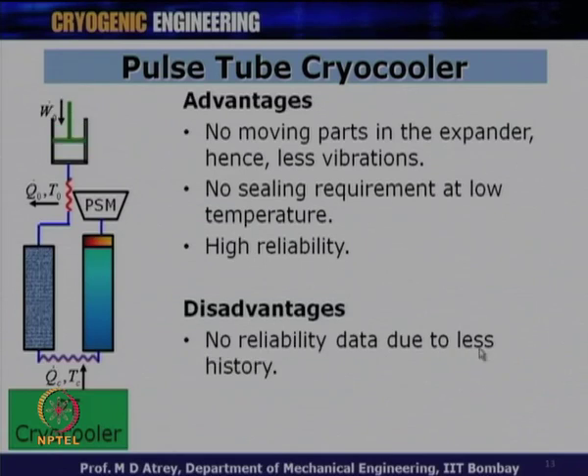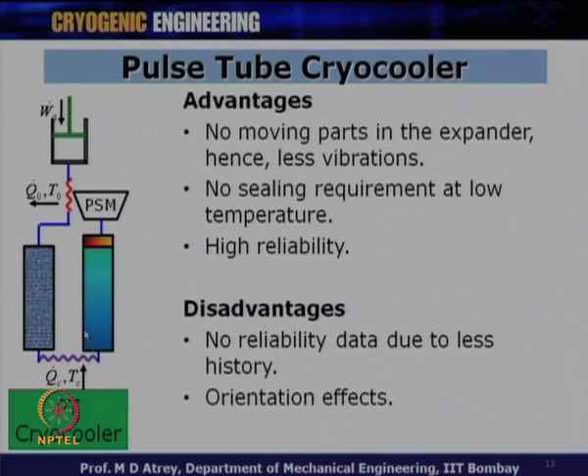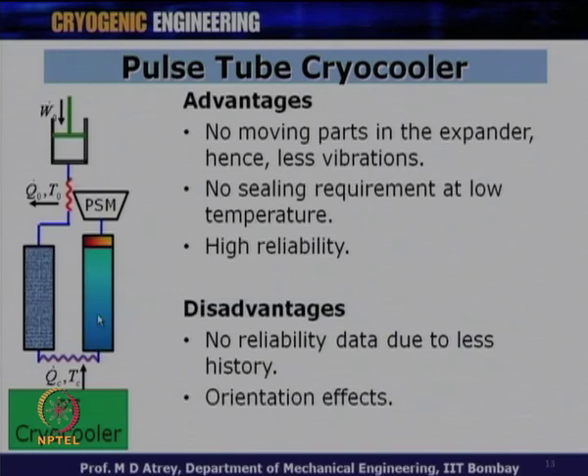The disadvantages are: there is no reliability data due to less history — no failure data over a period of time to conclude this cooler will never fail. Also, the pulse tube cooler is sensitive to orientation effects. Because it is gravity-driven with convective currents — hot end on top, cold end at the bottom — inclining the cooler at some angle produces a different cooling effect. Pulse tube coolers normally operate in vertical mode only.